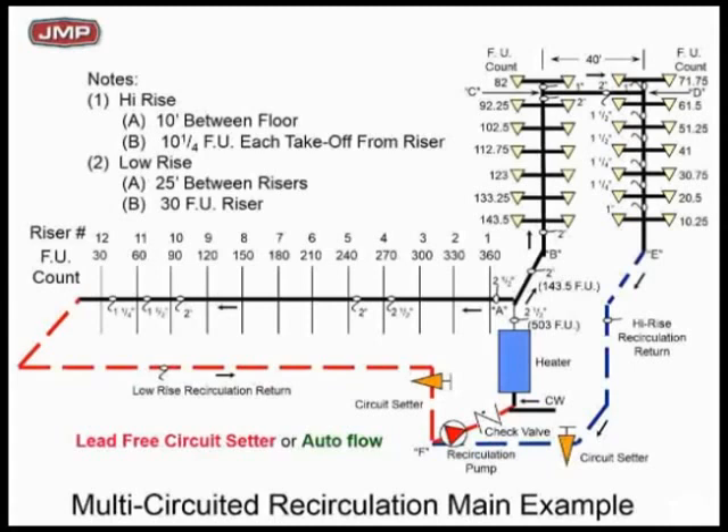This is a 2–3 GPM pump. How are you going to balance that? If you don't balance it, water's going to take the path of least resistance. The high-rise portion is going to get pretty good water supply and keep good hot water to the fixtures. But the low-rise section out of riser 12 is not going to get any hot water, so you're going to have a big problem at night when there's very little draw.